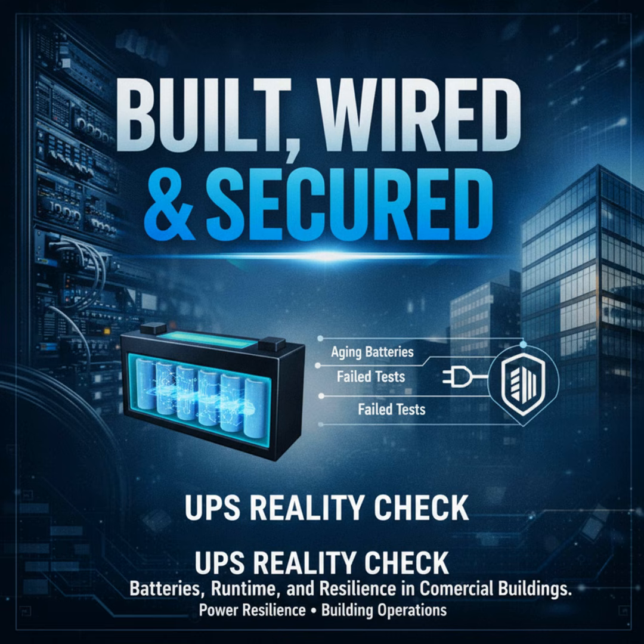Key takeaways. A short checklist listeners can use on the next site visit. First, identify critical loads and document runtime targets. Second, verify tests are performed at representative loads and durations and require trending data. Third, set battery replacement criteria tied to measured capacity, not just age. Fourth, consider distributed UPS for tenant-facing high-impact systems to avoid single points of failure. Fifth, assign clear ownership for maintenance, testing, and SLA accountability. Those 5 steps reduce surprises and make vendor conversations far more productive.